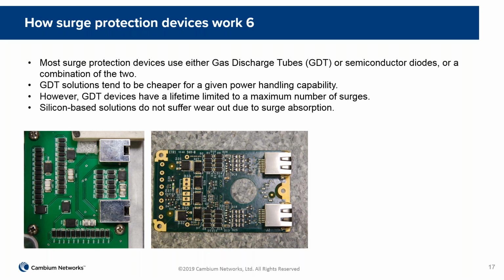Here we can see an example of 2 surge protection devices. So typically they use either gas discharge tubes, which work based on ionizing a gas when the voltage goes too high or exceeds a breakdown voltage across that junction within the device. And the device will actually glow, flash when the surge is being absorbed. So gas discharge tubes is one way, silicon or semiconductor devices such as Zeners and diodes is the other way. And sometimes, as in the example on the left here, we have a combination of the two.